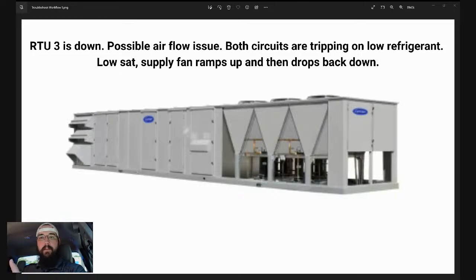Do we lose our supply fan signal? If we do, then I would venture to say that something may have broken inside of that board. But if we don't, or if the signal gets very weak but the output is still technically there, let's say that output is a 24-volt out. When it's just the supply fan running, we see that 24-volt out maintains 24 volts just fine. But then all of a sudden, when the contactor coil for the compressor gets engaged, that 24 volts drops down to 19 or 20. Well, that could be an indicator that we may have a transformer issue.